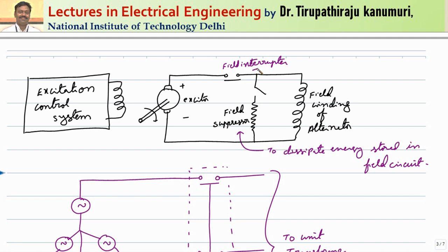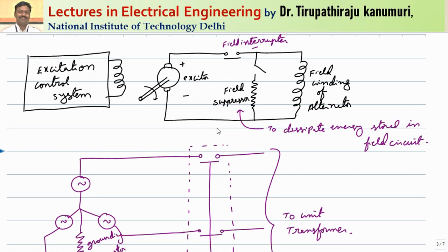Even if you remove the field interrupter, that is not going to be sufficient because the energy stored in the magnetic field cannot be removed immediately. In order to remove the energy stored in the magnetic field so that the flux will die out at a faster rate, a field suppressor resistor is used. Whenever the field interrupter switch is opened, this suppressor resistor is automatically connected. Whatever energy is stored in the field will be suppressed by this field suppressor, so the flux dies at a faster rate and the alternator will be safe.